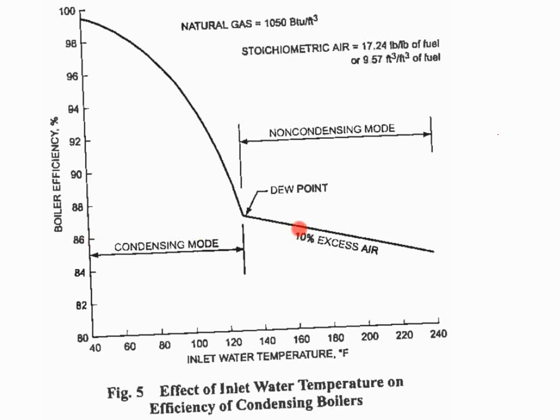If I ask it to make me hotter water, its efficiency will decrease. If I ask it to make me cooler water, its efficiency will increase. Then when I get to about 130-degree return water or so, a magical thing happens, and I actually am able to have cool enough water that it condenses the flue gases. And then that latent energy of the flue gases stays in the heat exchanger.